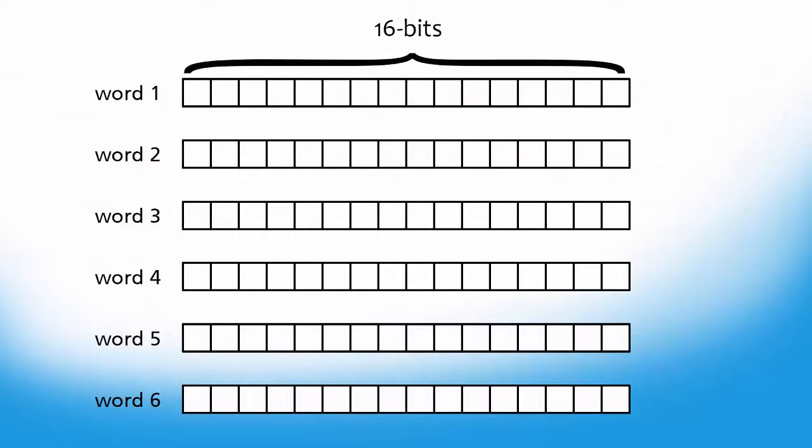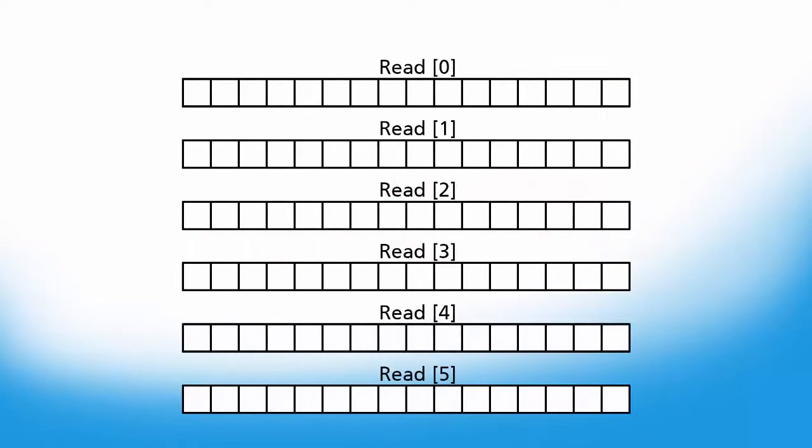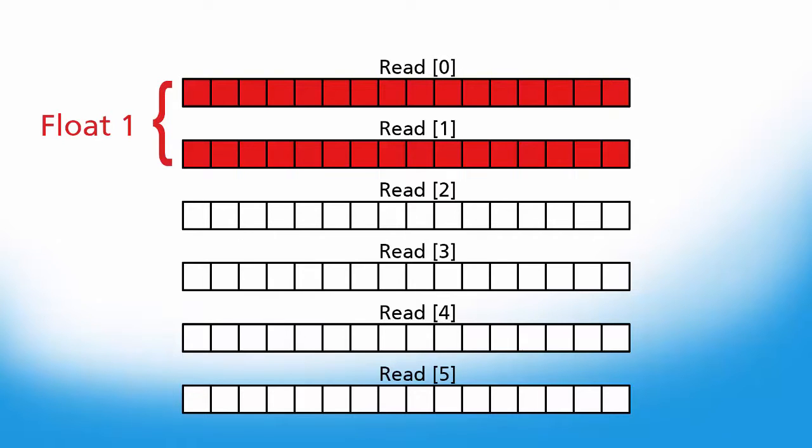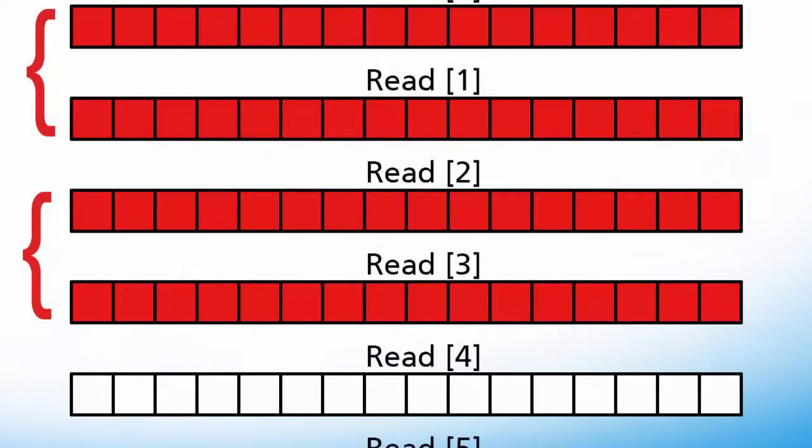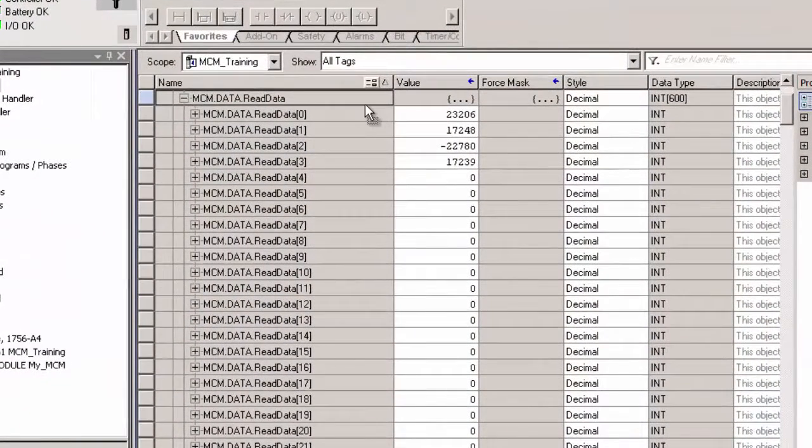Because our memory does not support 32-bit data types, the float values are broken up into two consecutive 16-bit integers each. Keep this in mind when you're mapping your data. The first float will occupy the first two addresses in my read data. The second float will be placed in the next two addresses. These four integers will be returned to the master and placed into the specified addresses in its database.